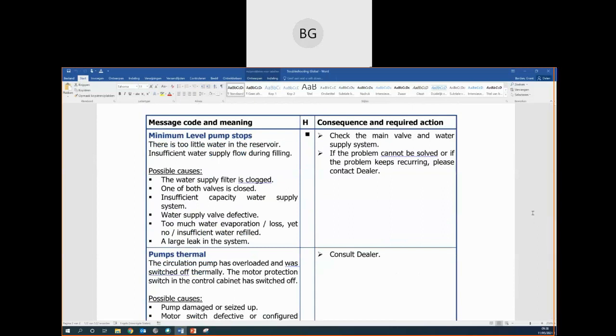Minimum level and pump stop. There is too little water in the reservoir, insufficient water supply flow during filling. Possible causes are the water supply filter is clogged. One or both of the valves are closed. Perhaps there is insufficient capacity of water in the supply system. The water supply valves are defective. Too much water evaporation or loss, yet insufficient water is supplied to the system. There could be a large leak in the system. Perhaps the container is damaged in some way. Check the main valves and the water supply system. If there is a problem, consult the dealer. And of course, check for any external leaks.